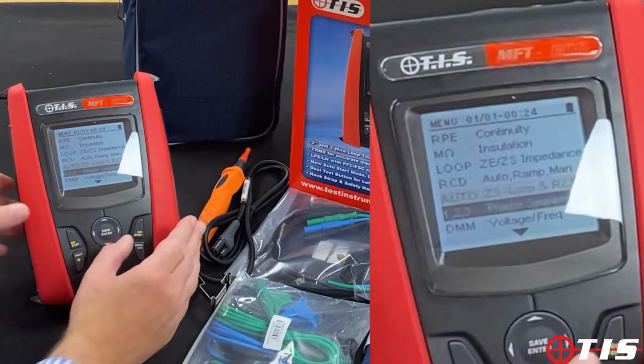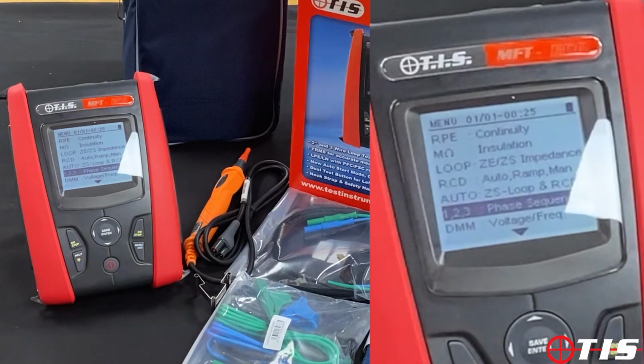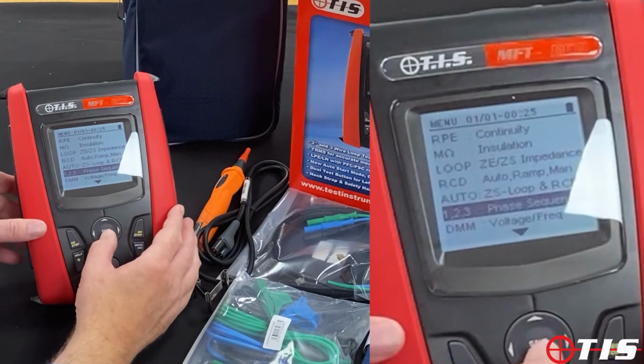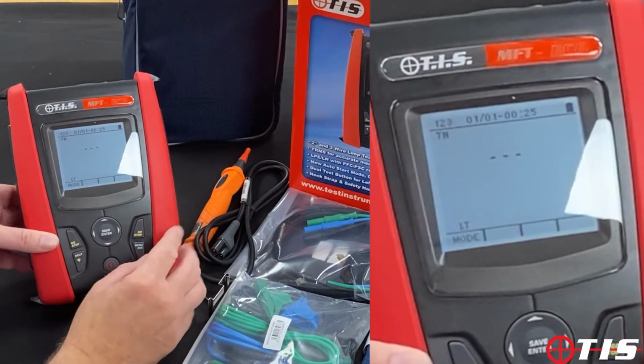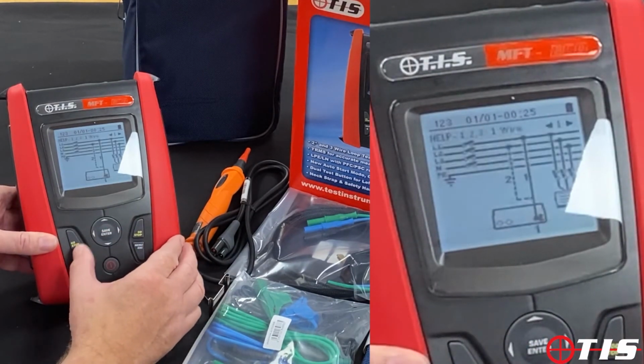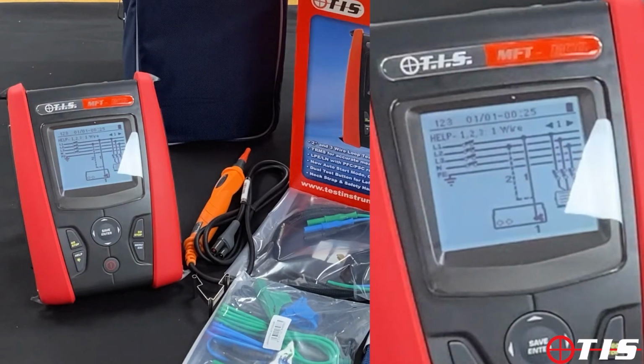The unit also has phase sequence, so if we're using it on 3-phase systems, which obviously we can, it's good for picking up phase sequence to make sure that we've connected a motor correctly. And on all of these settings, we have a help button. So whatever setting we're on, when we press help, it does a nice little diagram on the screen just as a reminder in case we've not got the instructions to hand.